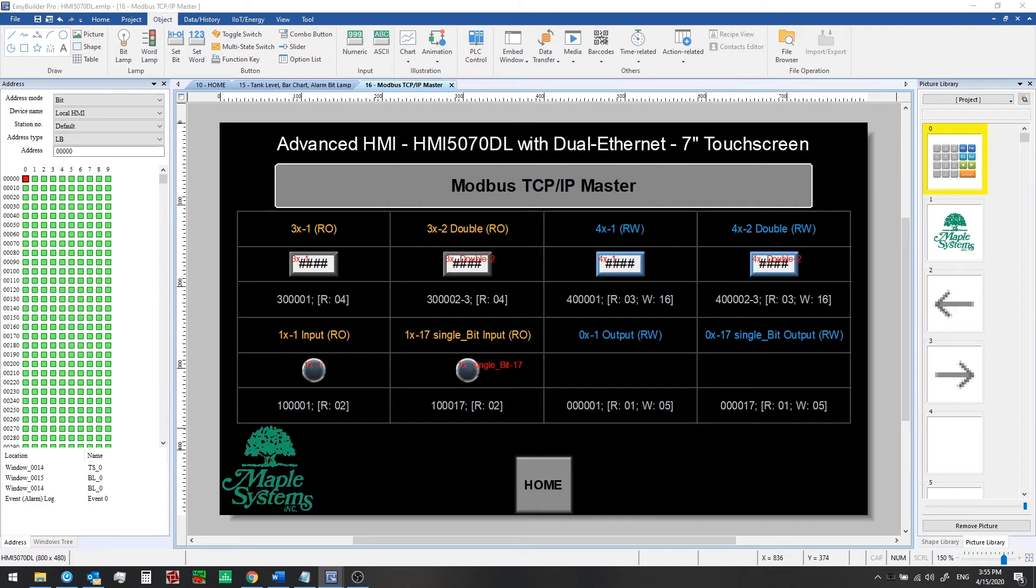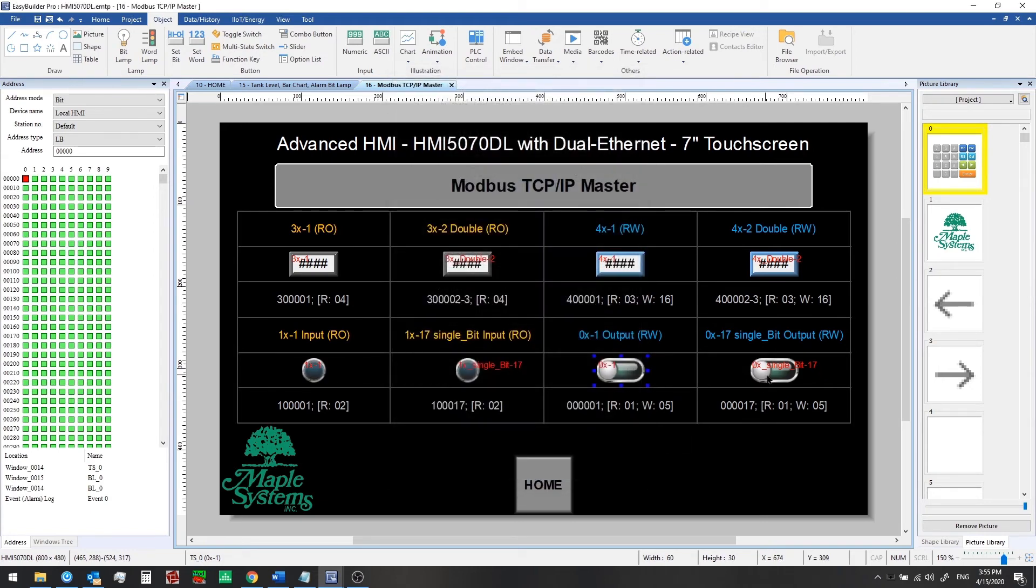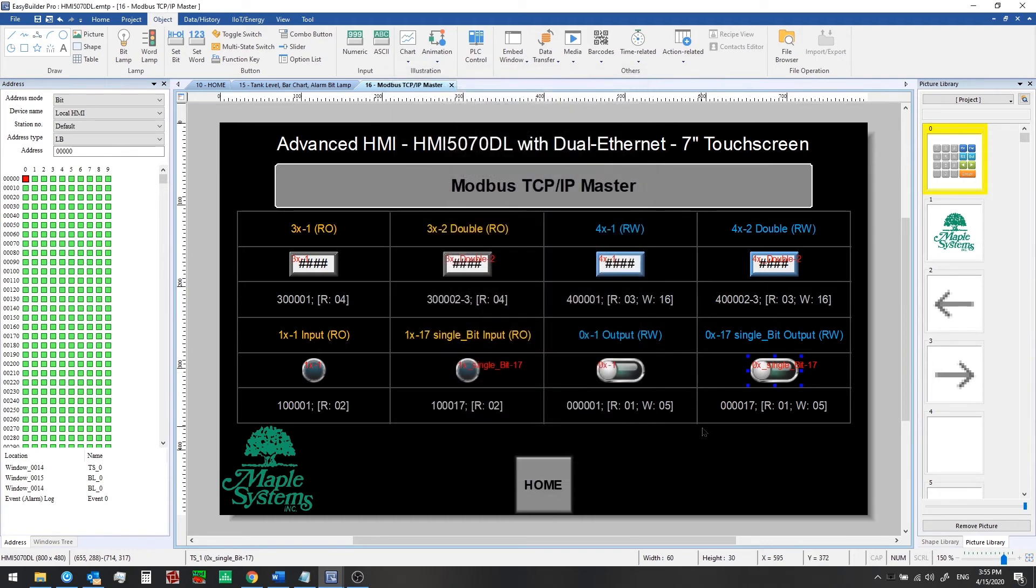We'll click OK there. Now we'll add some output coils. Here what we've got is a 0x1, so we can read and write to this coil. Again, it will try to read 16 bits at a time when you use standard 0x. And 0x1 single bit will just read one single bit or write one single bit at a time. So we have 0x1 single bit 17 selected. At this point, we're ready to run our simulation.